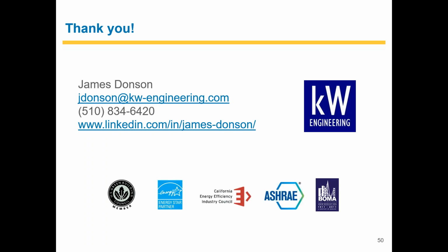Yeah, so in my opinion, TLEDs are not the greatest selection for retrofit, primarily because they rely on the existing fixture optics, and those existing fixture optics can be pretty inefficient. They're not a good fit for direct and indirect pendants because they generally only produce light in one direction. Be very careful when you see lamps that report a 320-degree beam angle. It's actually a 320-degree field angle. What you get above maybe 170 to that 320 angle, the light that comes out of that radial section is generally about 10% of the total lamp lumens. So you're not going to get a whole lot of uplight out of those lamps, so I'd be careful.